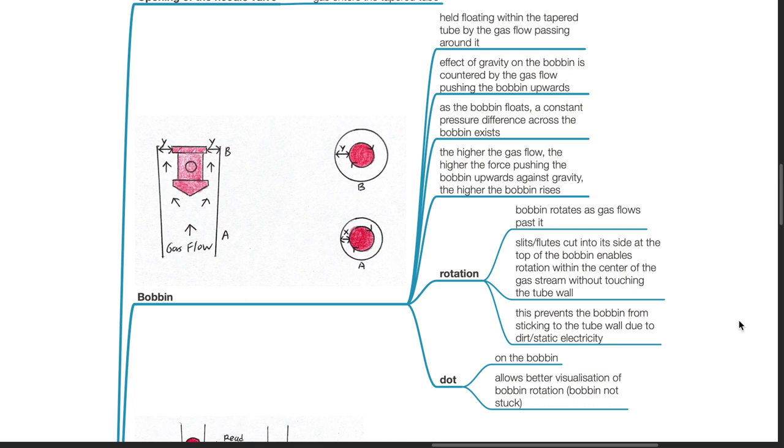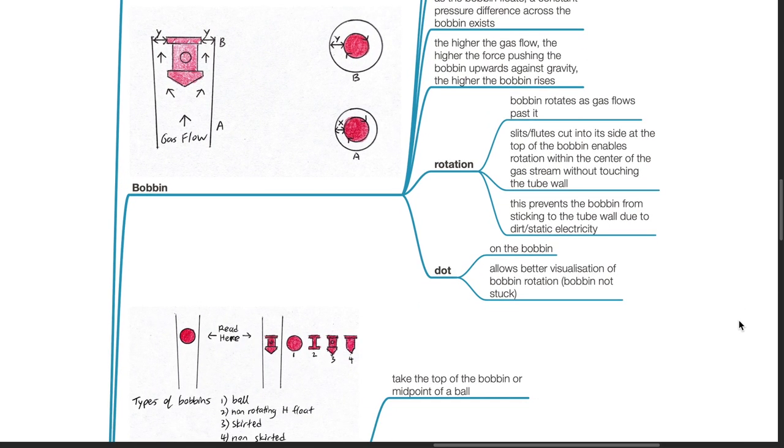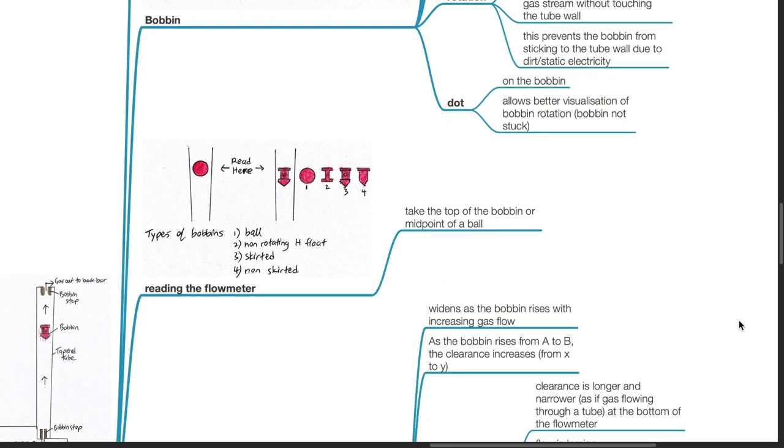Rotation: The bobbin rotates as gas flows past it. Slits or flutes cut into its side at the top of the bobbin enable rotation within the center of the gas stream without touching the tube wall. This prevents the bobbin from sticking to the tube wall due to dirt or static electricity. The dot on the bobbin allows better visualization of bobbin rotation and indicates that the bobbin is not stuck.